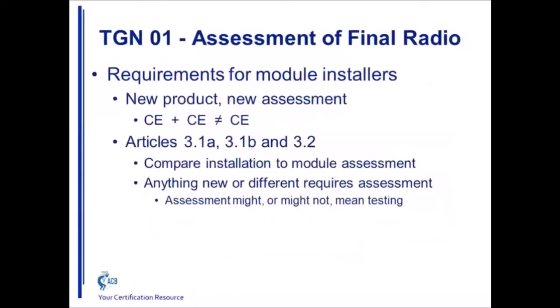Under the long-standing CE marking regimen, we say CE plus CE does not equal CE. What does that mean? You might have a CE-marked radio module that you're putting into an existing CE-marked product—that happens quite often—but you cannot simply do nothing. You have to do some kind of assessment against the articles under the Radio Equipment Directive. You might compare that installation to the module's original assessment, and anything new or different requires reassessment. It may or may not mean more testing—again, it depends on the case.